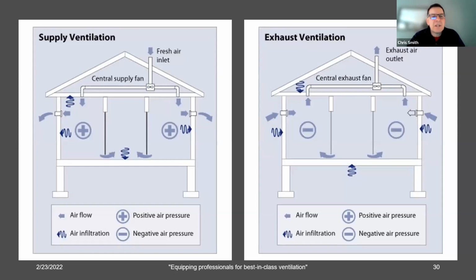Supply ventilation is basically where a fan is pulling outdoor air in and blowing it into the house. And so what happens as we blow outdoor air into the house is we're bringing in some fresh outdoor air. We're positively pressurizing the house. And then because the house is under positive pressure, indoor air is being forced out of the house through, again, whether it's open windows, vent of some sort, most likely some sort of exfiltration through cracks and leaks. So that's supply ventilation.